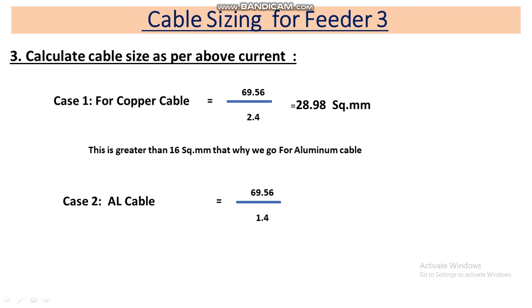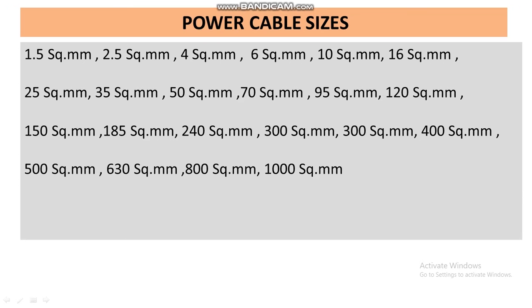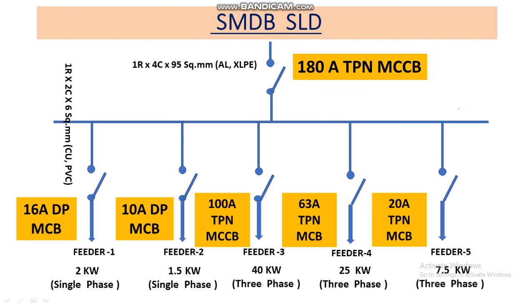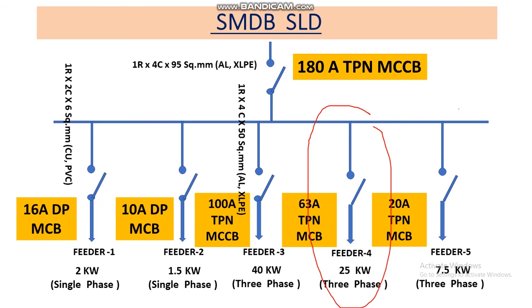For aluminum cable for Feeder 3: 69.56 ÷ 1.4 = 49.68 square mm. Looking at the cable selection chart, 49.68 is near 50 square mm, so we select 50 square mm. Our proposed cable size for Feeder 3 is 1 run, 4-core, 50 square mm aluminum XLPE cable — 4-core because it is a three-phase and neutral system. In this way we can calculate the cable size for all feeders as per load.